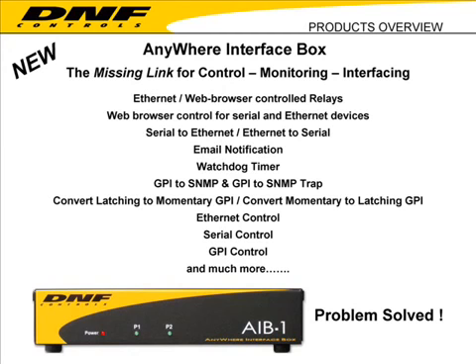The Anywhere Interface box also supports watchdog timers. You can configure a timer so that as long as it's receiving GPIs from some external device, receiving serial data, or receiving Ethernet data, that timer keeps resetting. If I lose my serial connection, the watchdog timer would time out, cause a GPO to turn on, or send an Ethernet message telling someone they've got a problem they need to address.